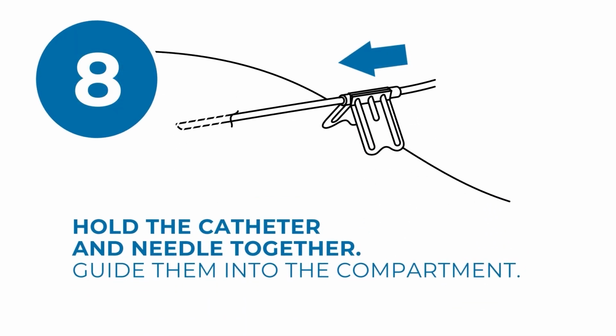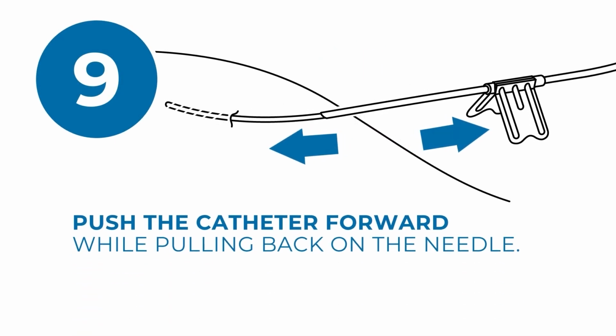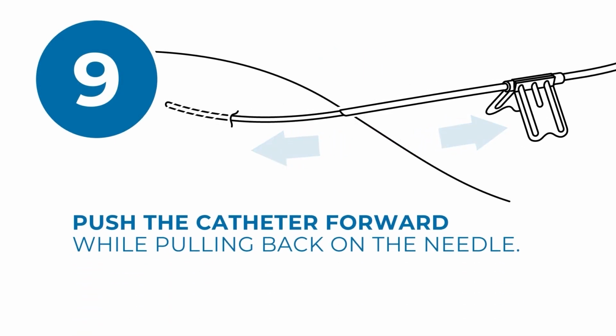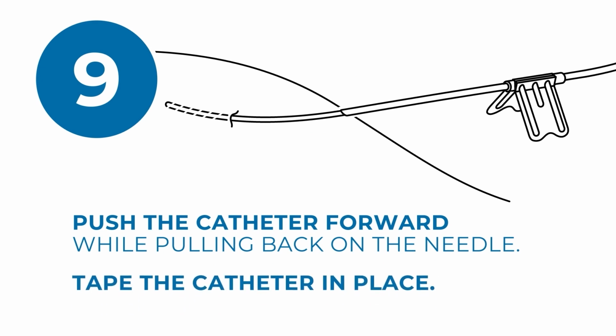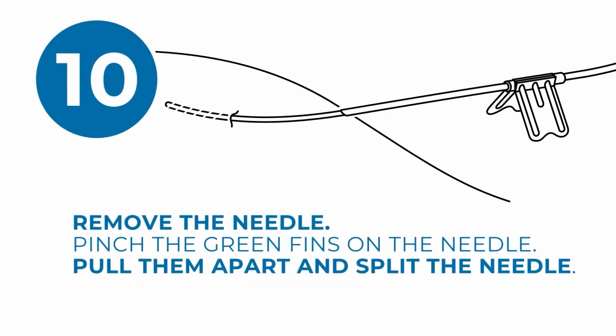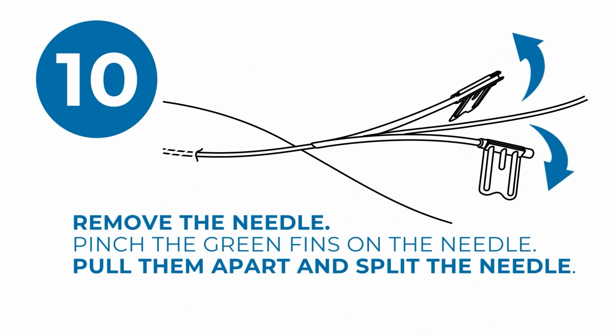Next, hold the catheter and needle together. Ensure the tip of the catheter is protected inside the needle and simultaneously guide them into the desired compartment. Push the catheter forward while pulling back on the needle. Once proper insertion is achieved, tape the catheter in place after the needle is out of the skin. Now, remove the breakaway needle by pinching the green fins on the needle together. Then, pull them apart and split the needle away.